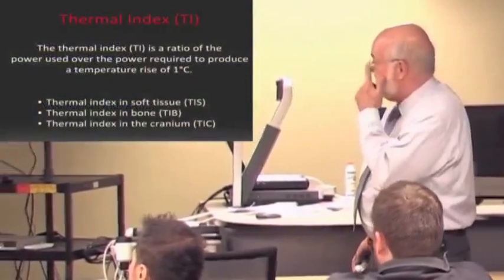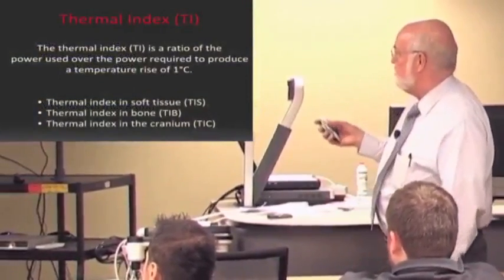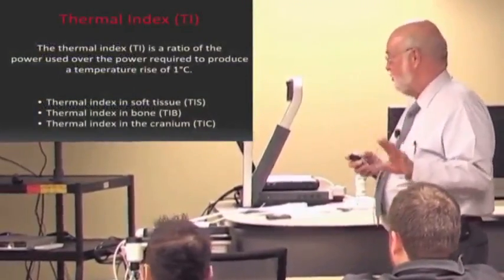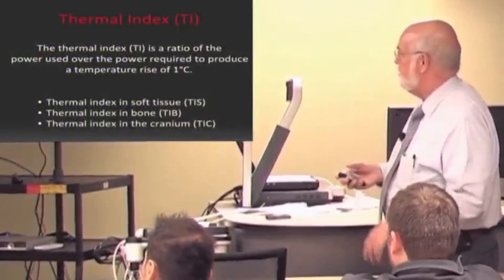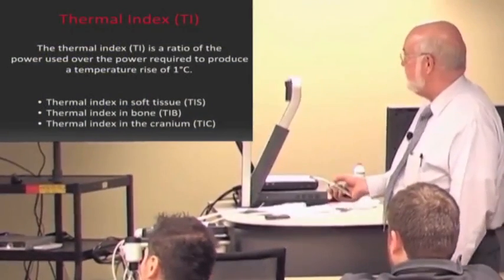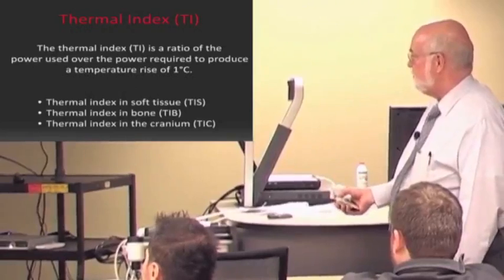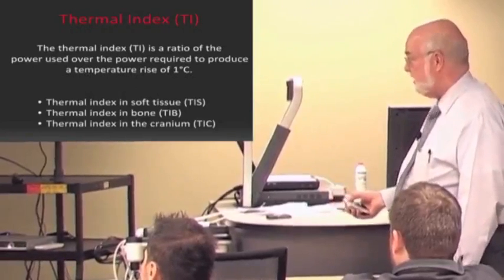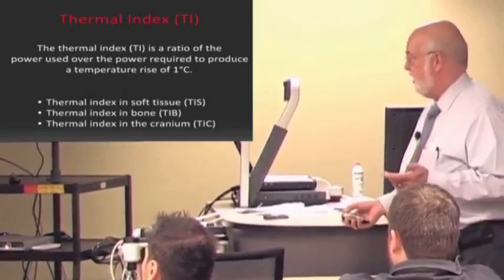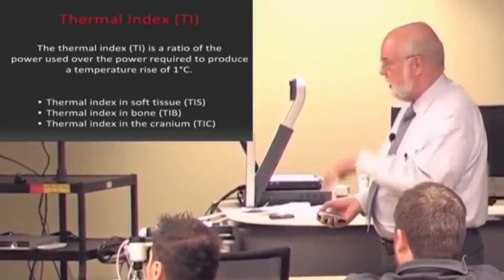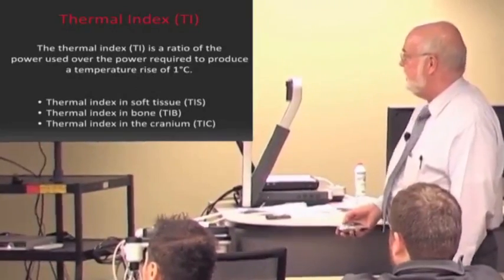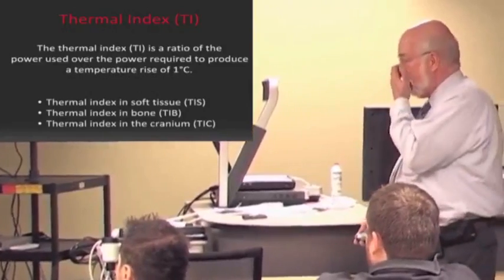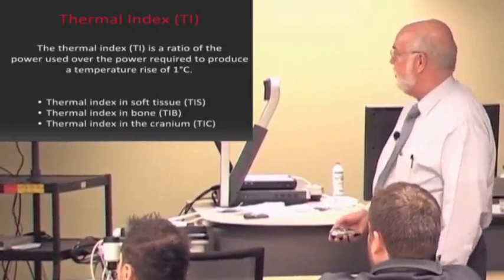So again, the thermal index is a ratio of the power used by your particular piece of equipment on that patient at that moment compared to the power that it would take to produce a temperature rise of 1 degree centigrade in that tissue. So usually it's a small fraction of that, but it's kind of useful to have that information up there to remind you that yes, indeed, we are putting energy in and we should account for it.